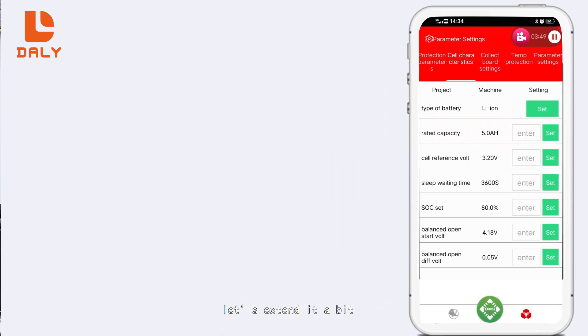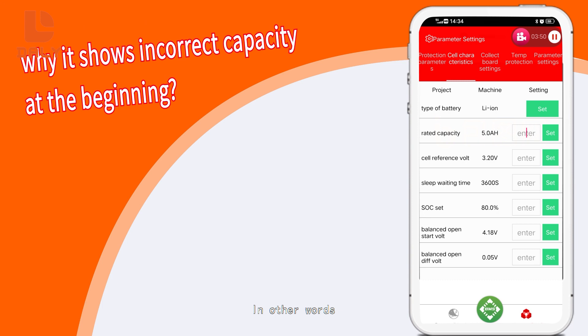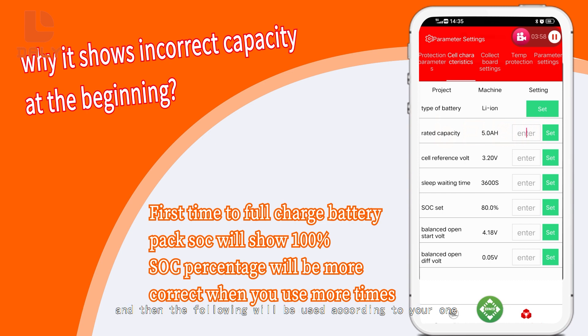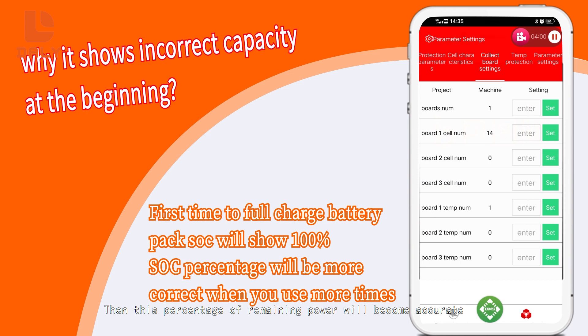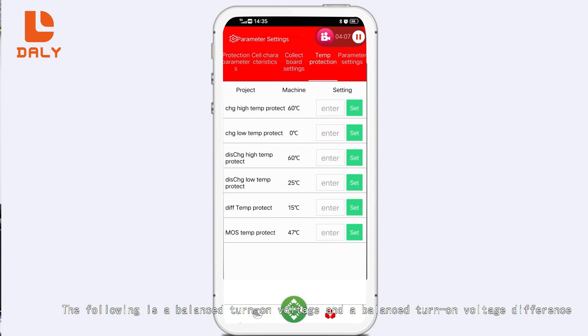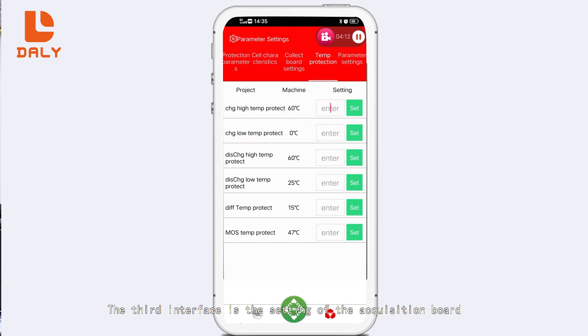Only after setting the capacity here will the real-time remaining power percentage be accurate. The following settings include sleep waiting time and a manually set SOC power ratio. Also, why is the battery display inaccurate when first installed? When you are fully charged for the first time, the protection board will automatically calibrate to 100% power. After that, the remaining power percentage will become accurate. The following settings are balanced turn-on voltage and balanced turn-on voltage difference.